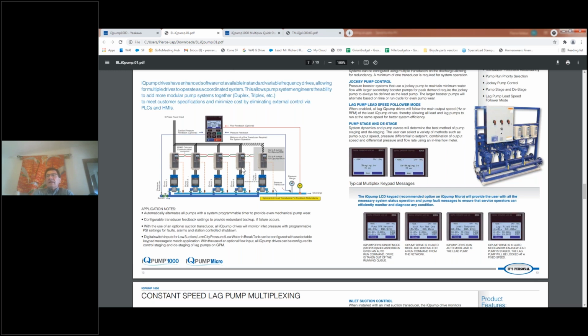Now, the single 800 horsepower drive in this scenario is a single point failure. It goes down, you get no water. In the case of the multiplex system, if a drive fails, you get water, and you're probably still meeting your full demand. Even if 2 drives fail, you're still getting 400 horsepower worth of pumping capability, and that can get you through the situation till you can get the 3rd and then the 4th unit repaired. So you see the efficacy.